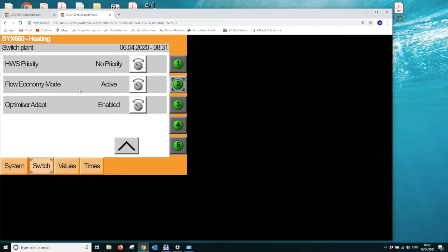Flow economy mode is a feature of the controller that has an energy saving benefit. It is to do with the controller identifying that, on a particularly mild day with a warm room temperature, which is above or very close to set point, the actual heat input into the system will be very low. So if you have a set point calculated for the radiators which is within 3 to 5 degrees of the calculated flow set point, then the flow economy mode will become active and it will disable the heating.